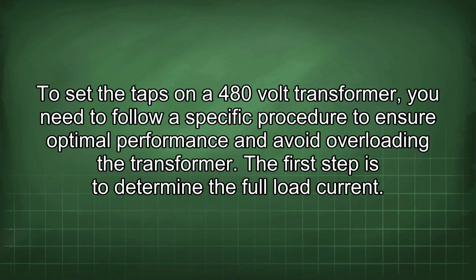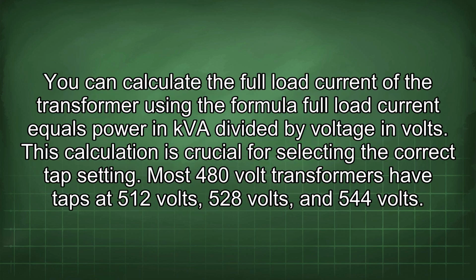To set the taps on a 480-volt transformer, you need to follow a specific procedure to ensure optimal performance and avoid overloading the transformer. The first step is to determine the full load current. You can calculate the full load current of the transformer using the formula: full load current equals power in kVA divided by voltage in volts. This calculation is crucial for selecting the correct tap setting.